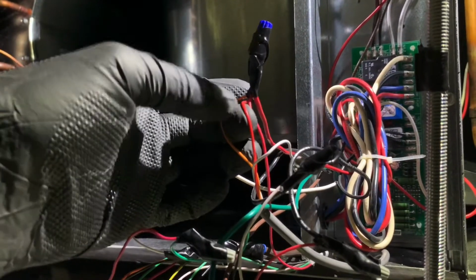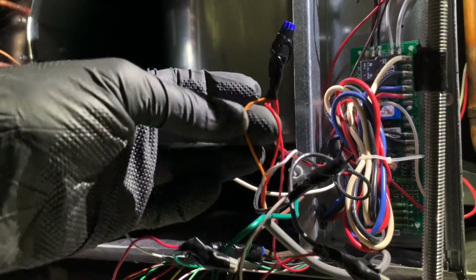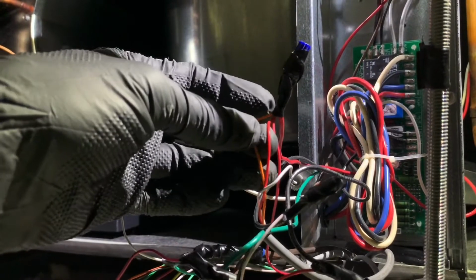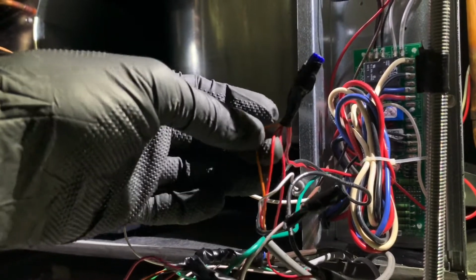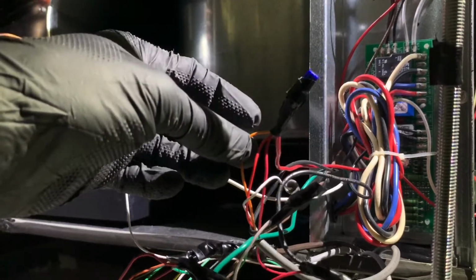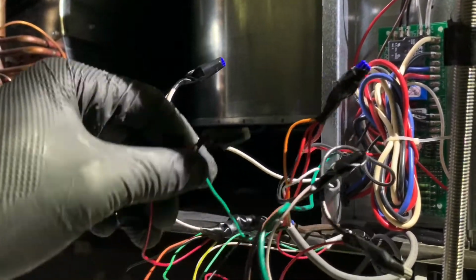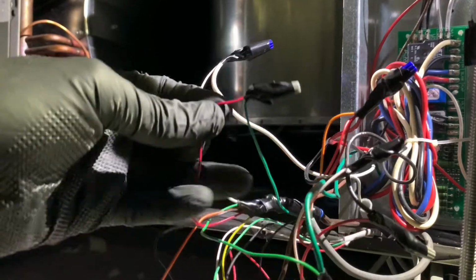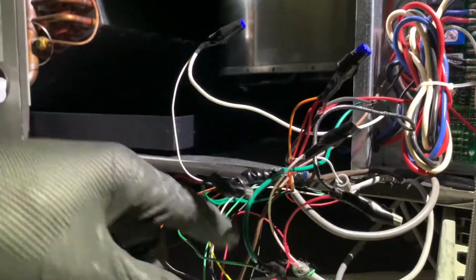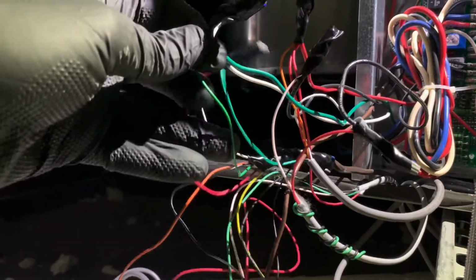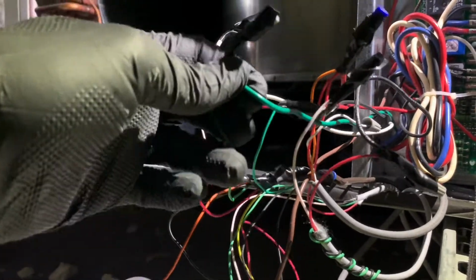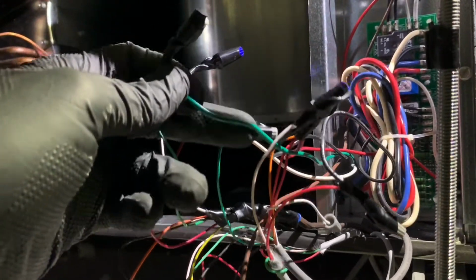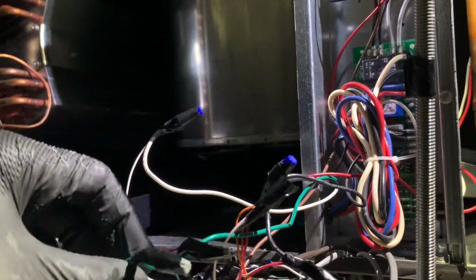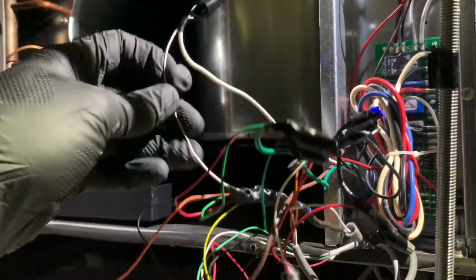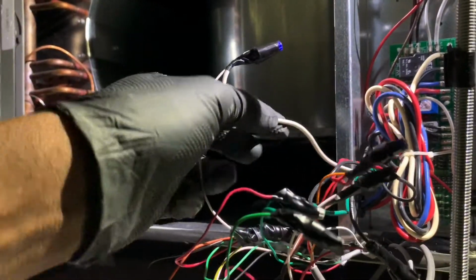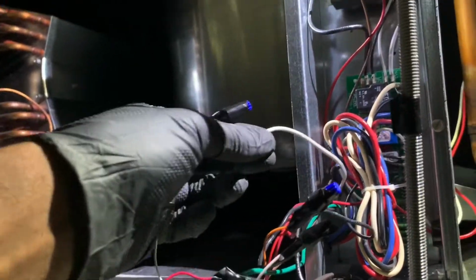And this 24 volts goes into the flood detector, and this orange wire takes that same 24 volts from the flood detector, because it's on 24 volts as well, and brings it back up here on the green wire, goes into my thermostat. And of course we know this is the green wire from my thermostat right here, and it goes into the green wire into my air handling unit for the fan. And this is the white wire from my thermostat right here, and it goes into the white wire that goes into my air handler for heating.